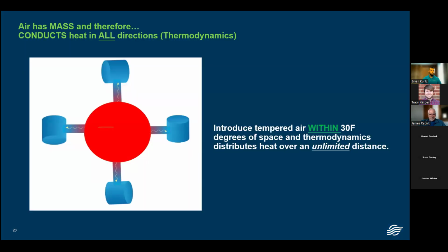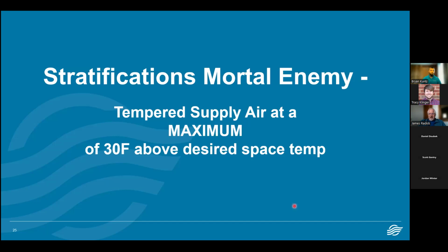Can you go back to that a second, Brian? And then we can also ensure that we don't have that stratification issue because our control system not only monitors that positive pressure and reacts to it by varying the amount of outside air and return air mix, but it also monitors the space temperature. And we have parameters in there so that even if your space cooled down on a weekend below 60 degrees and you wanted 65, the worst thing you can do is throw high temperature air in it. Get that heat into the space, get that heat. No, what'll happen is you're going to get high levels of stratification occurring.